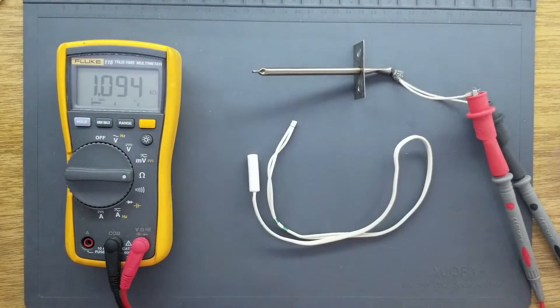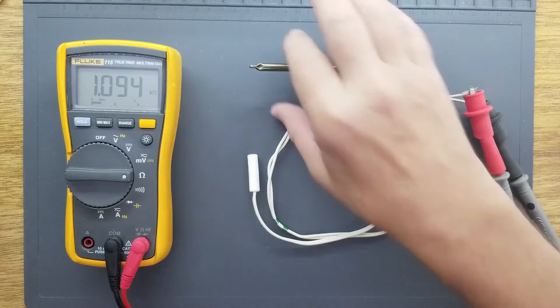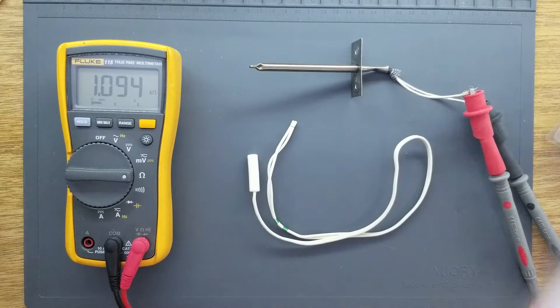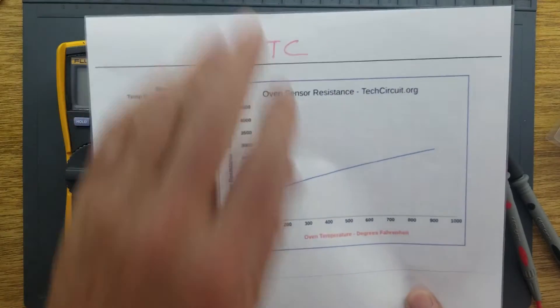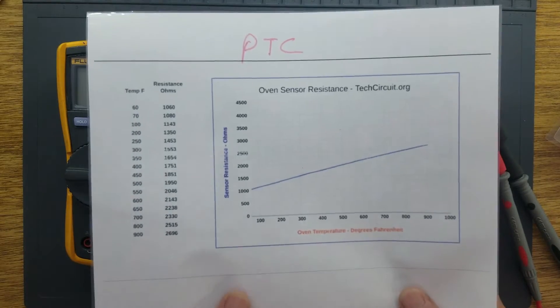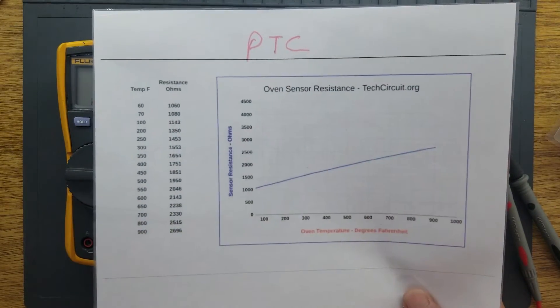This is an oven sensor, and this is known as a PTC thermistor. PTC means positive temperature coefficient, and that means that as the temperature increases, its resistance increases.